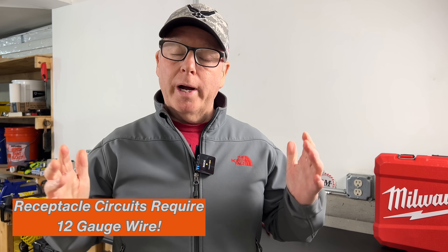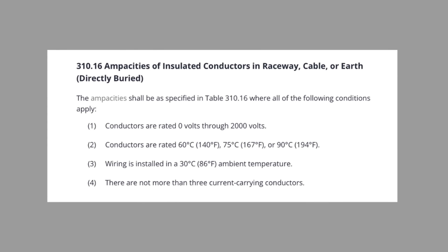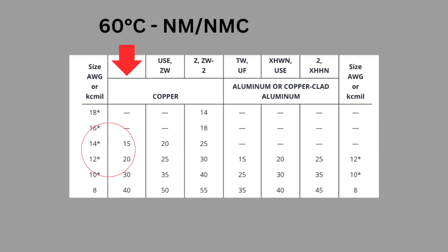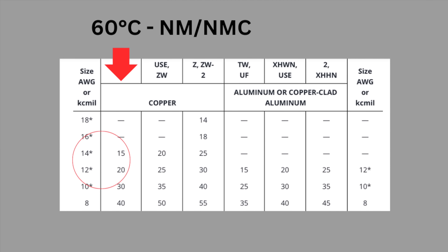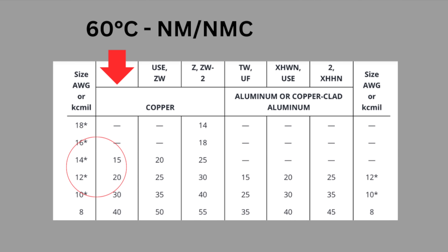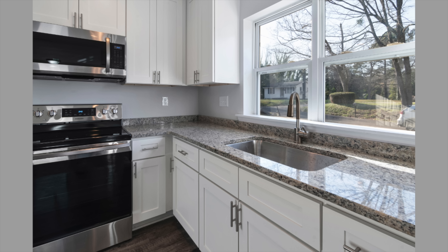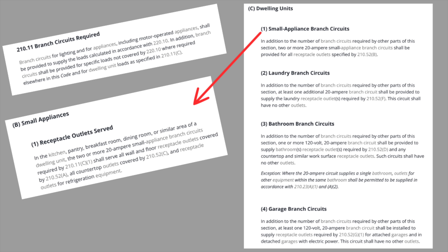In any other location, any orientation is going to be code compliant. False claim number three: receptacle circuits require 12 gauge wire. Article 310.16 covers the ampacities, or current ratings, of conductors, and we size our wires based on the values listed in these tables. 120-volt receptacles in a home require 12 gauge wire for 20 amp circuits and 14 gauge wire for 15 amp circuits. But 20 amp circuits and 12 gauge wire are not required everywhere. Article 210.11(C) tells us the areas in the home that do require 20 amp circuits: kitchen countertops, bathrooms, laundry rooms, and garages. Many 120-volt receptacle circuits in a home are 15 amp running 14 gauge wire. You can spend the extra money and run 12 gauge wire for all your receptacle circuits, but it isn't required by the NEC.